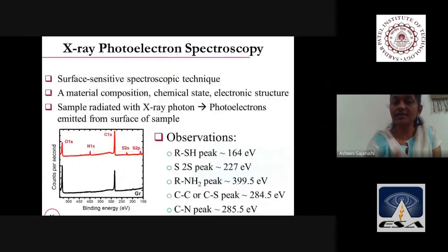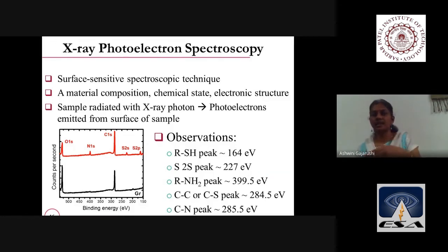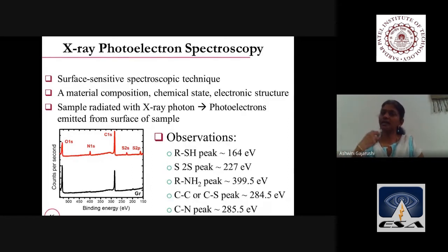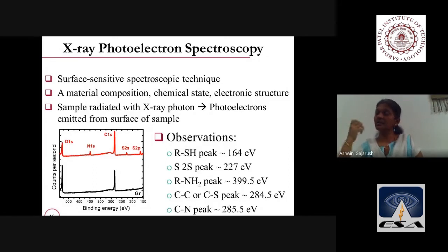One more system is the XPS. XPS is X-ray photoelectron spectroscopy. We have seen SEM, the scanning electron microscope, where only electrons are involved. Now in XPS, photoelectrons are involved. Photoelectrons means the sample is irradiated with X-ray photons, and then it emits photoelectrons. Those emitted photoelectrons are collected by the detector system, and then it gives the surface phenomenon, what is happening at the surface.